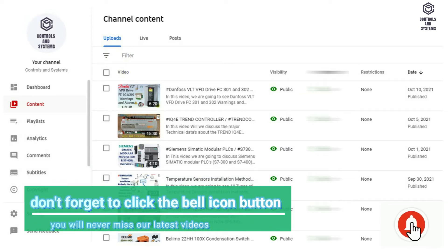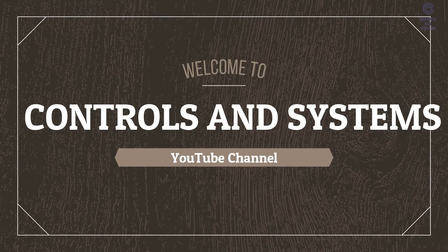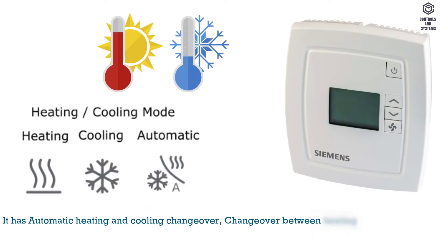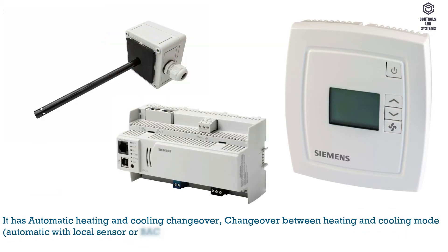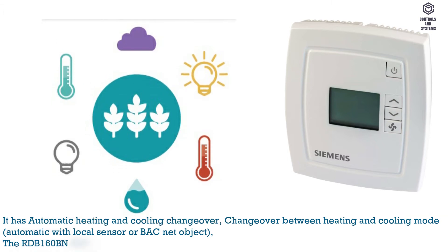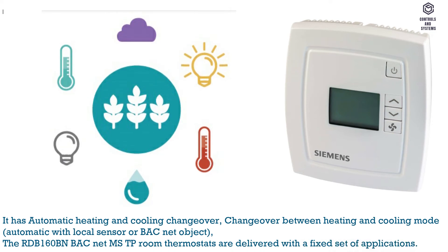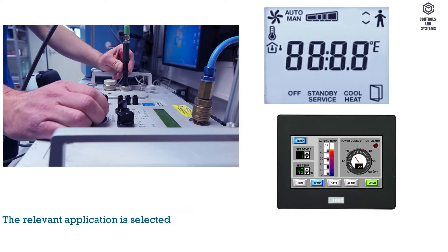Welcome to the Controls and Systems YouTube channel. Overview: it has automatic heating and cooling changeover — changeover between heating and cooling mode is automatic with local sensor or BACnet object. The RDB 160BN BACnet MS/TP room thermostats are delivered with a fixed set of applications; the relevant application is selected and activated during commissioning.